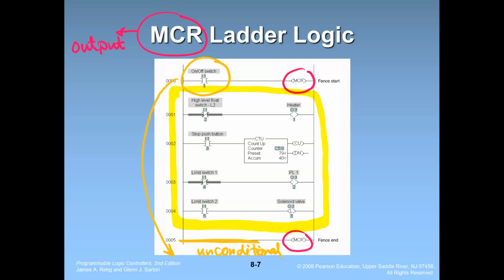So I'm going to write what will happen based on the condition of our on-off switch. If the bit here is equal to 1, then it means that you have continuity. And with continuity, then rungs 0, 1, 2, 3, 4, 5, 6 will be executed like this. So all these will be executed and then it will go to the rung after the second MCR. So basically if your condition of MCR is true, then your program will be executed as normal.